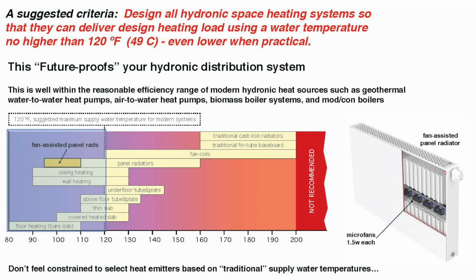These are available in Europe. I think you're going to see them within the next couple of years in the North American market. These are little tiny fans that run on about 1.5 watts apiece when they're at full speed. They enhance the convective output at low water temperatures. So why would a manufacturer put fans in panel radiators? Because they want to sell those radiators into a market that is moving towards heat pumps and away from high temperature fossil fuel heat sources.